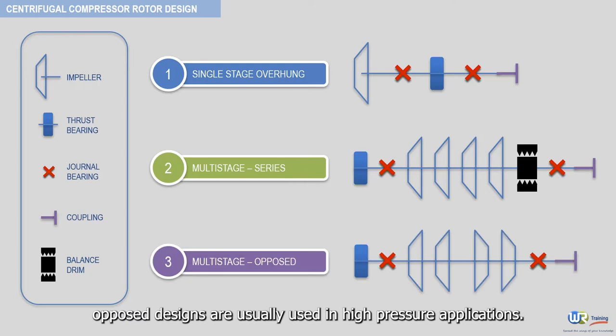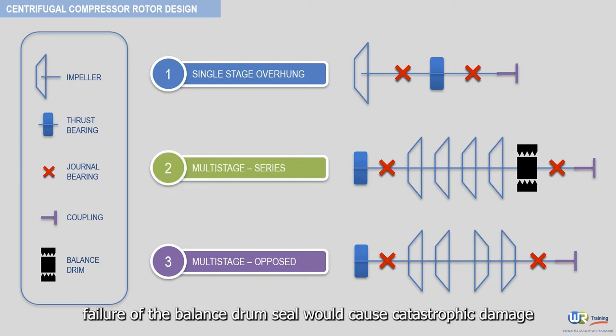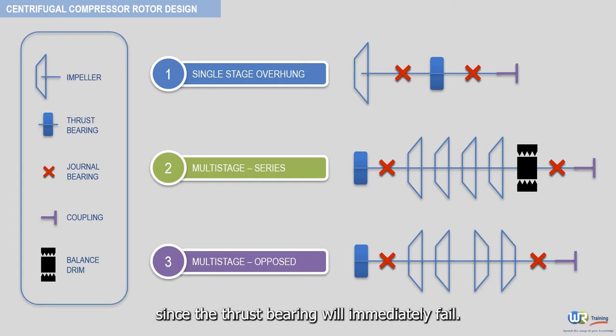However, if the rotor were a series configuration as seen here, failure of the balance drum seal would cause catastrophic damage since the thrust bearing will immediately fail.